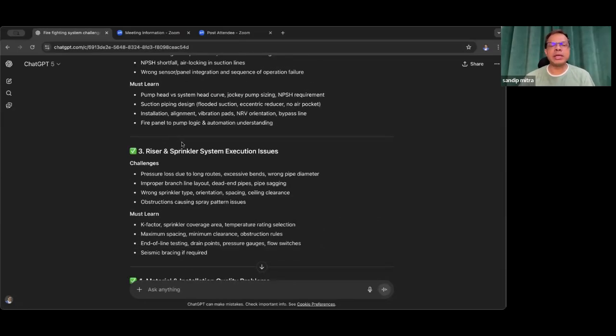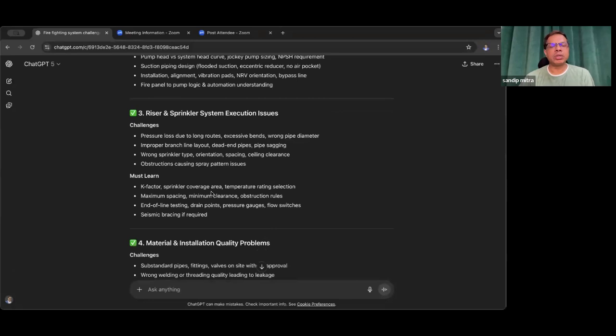Number 3, riser and sprinkler system execution issues. The pressure loss challenges. What are the challenges? Pressure loss due to long routes, excessive bends, wrong pipe diameter, then improper branch line layout, dead end pipes, pipe sagging, wrong sprinkler type, orientation, spacing, ceiling clearance, and obstructions causing spray pattern issues. Then what you need to do: you must learn the K factor, the sprinkler coverage area, the temperature rating selection, maximum spacing, minimum clearance, obstruction rules, end of line testing, the drain points, the pressure gauge, flow switches, and seismic bracing if required.